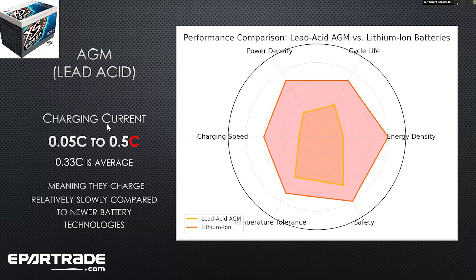So let's say, for instance, we have a 100 amp hour battery, and we're going to charge it at 0.5 C. That's 0.5 times 100, that would be 50 amps. And at 50 amps, we would expect the battery to be full, in theory, in 2 hours. In lead acid, that's not necessarily true, it's going to be longer than that. But lead acid batteries are typically about 0.3 C, about 3 hours of charge rate, about 33 amps for a 100 amp hour battery. So you can quickly see the lead acid battery is limited in its ability to accept energy fast.